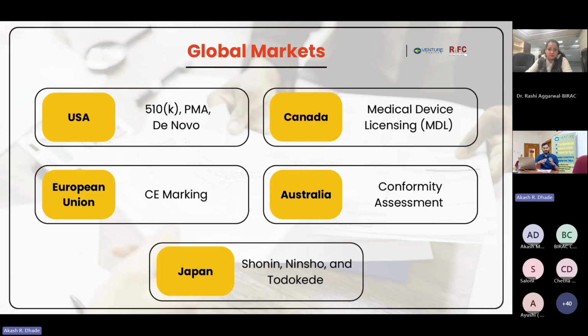So the basics is if you are going in different markets across globe, their requirements will be different in certain aspects. However, if you think combiningly, what they need is assurance that your device functions as intended and it does not pose any risk to the patient. So, from the design point of view, if you are starting your design, if you take a risk-based approach, for example, if you think what is the medical condition I'm trying to cater, and what are the risks associated with that medical condition, and what is the harm my device can pose to these patients, then you will be in a position to create documentation which are required by these regulatory authorities.